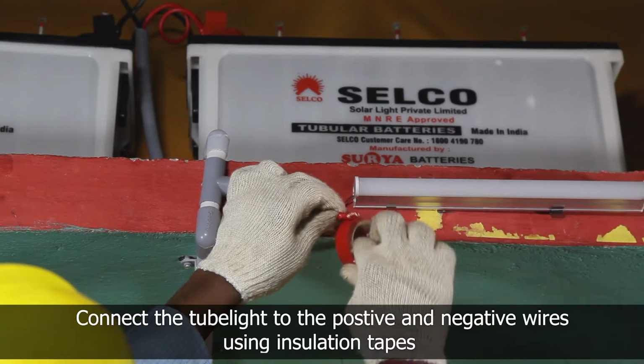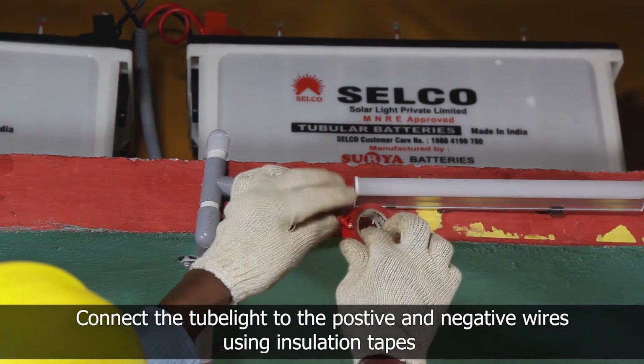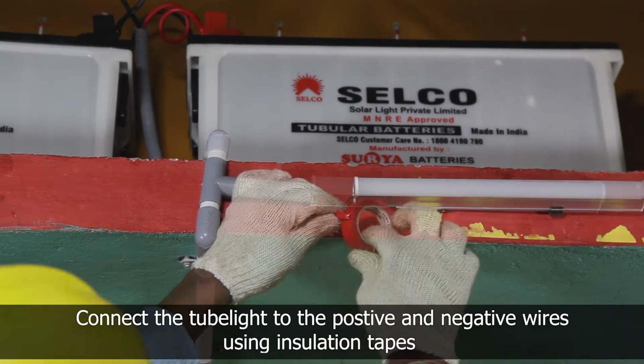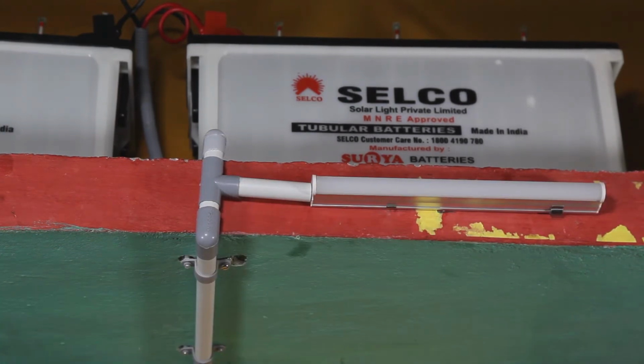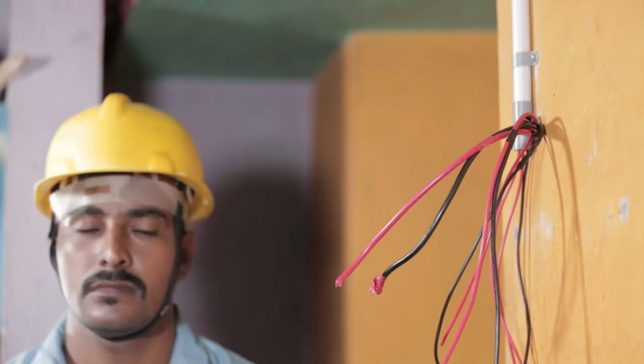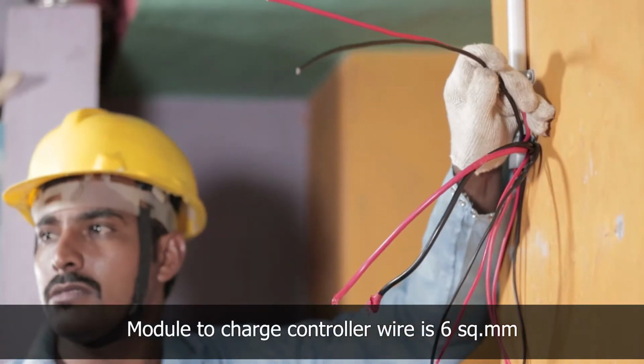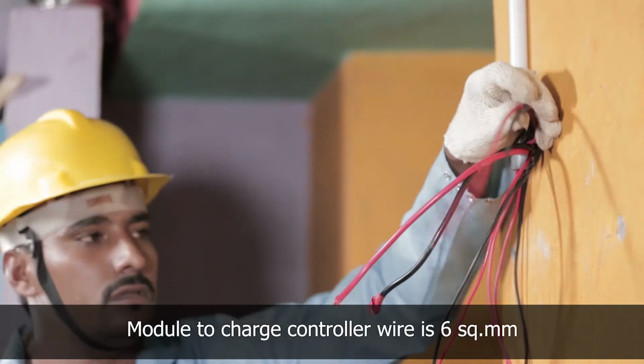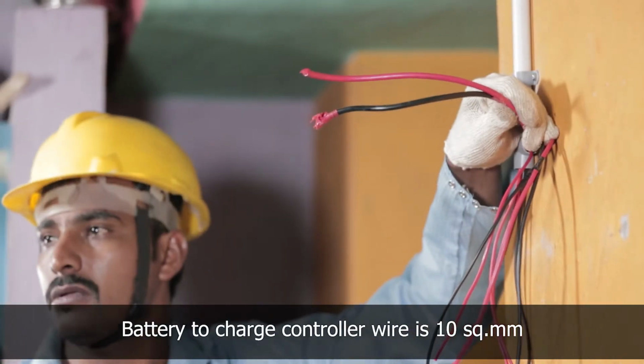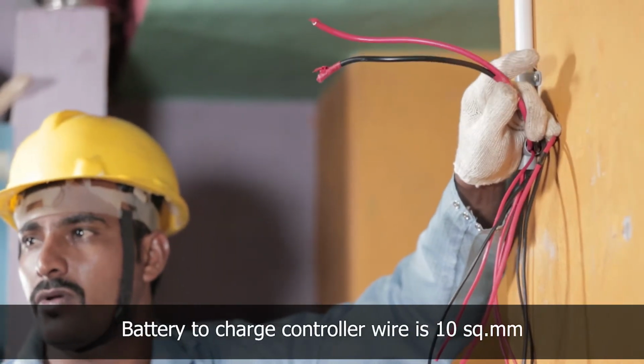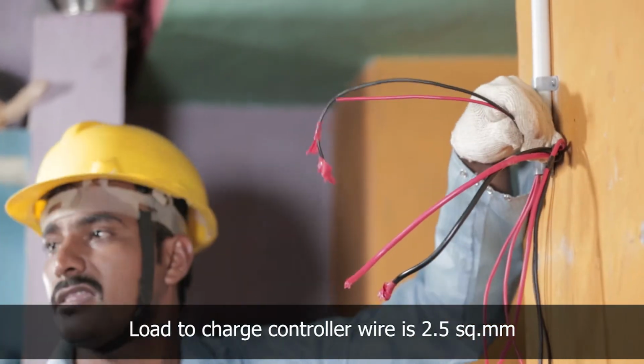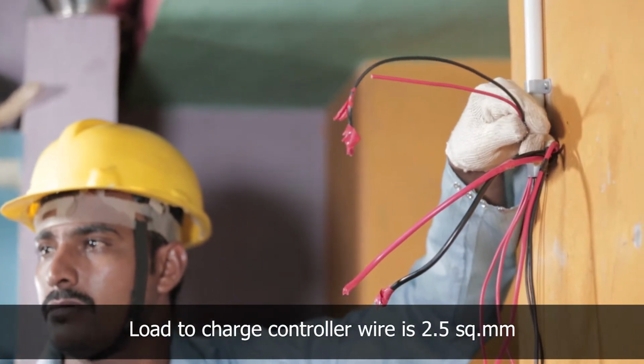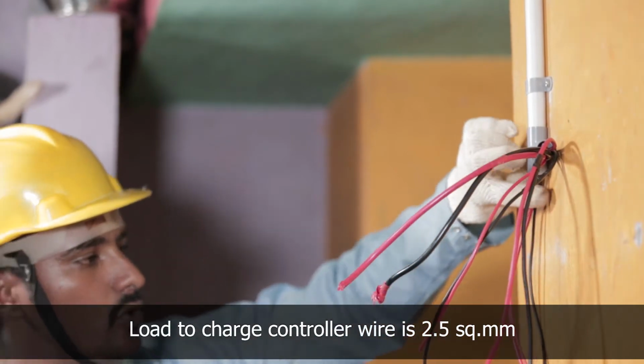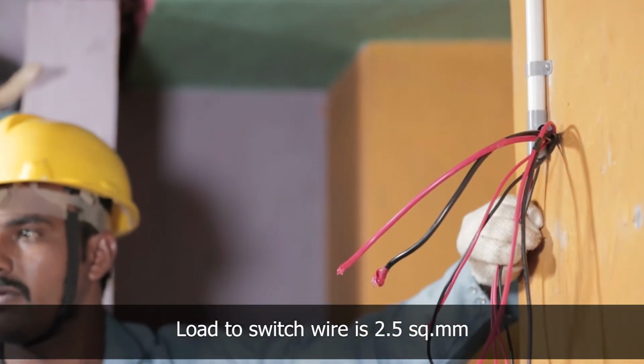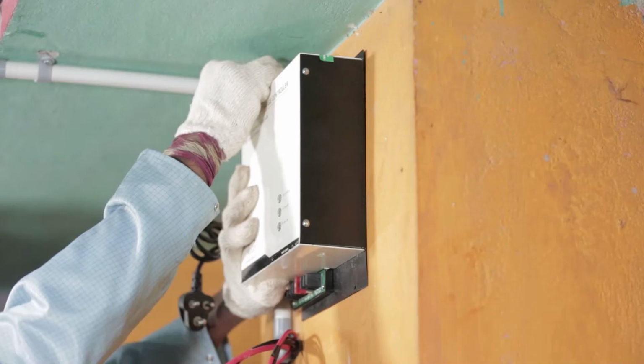All the positive wires are insulated using an insulation tape to avoid short circuit. Module to charge controller wire is 6 square mm. Battery to charge controller wire is 10 square mm. Load to charge controller wire is 2.5 square mm. Load to switch wire is 2.5 square mm.